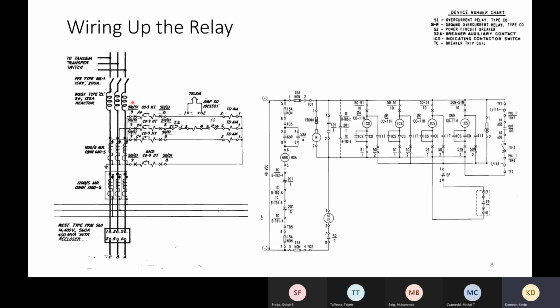So we went from the 1 line to looking at a 3 line. Here we have our bus. In this case, we actually had some reactors to lower fault current. And when you talk protection, you have to talk about a protective system. A lot of people think when you think protection, it's just the relay. Well, if the relay operates and there's no DC, then I can't energize the trip coil. So that's no good. So the DC system is actually part of the protective system. The relay is part of the protective system.